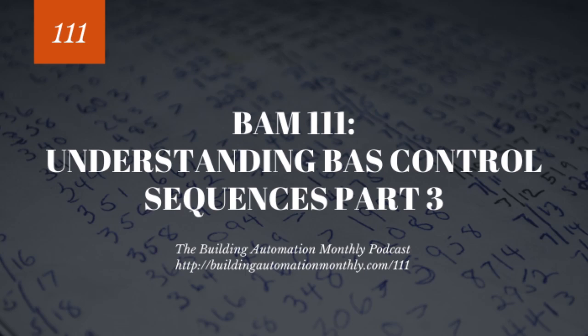When that tonnage that you calculate gets higher than the tonnage capacity of the chiller that's running. And that's a really cool scenario because you could do really cool things, right? You can have, for example, a 400-ton chiller, a 200-ton pony chiller, and another 400-ton chiller. If the load is 500, you could bring on that 400-ton and a 200-ton. So you're running that 200-ton maybe at full load, but you're running that 400-ton at 300, which is kind of a sweet spot, right?